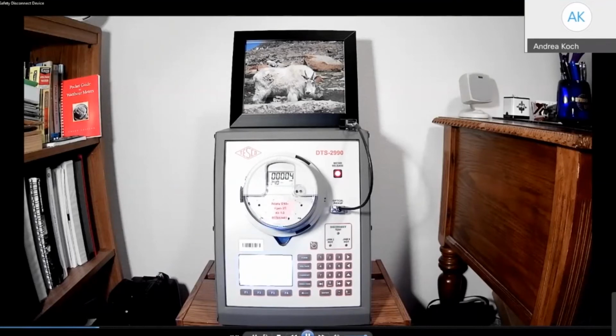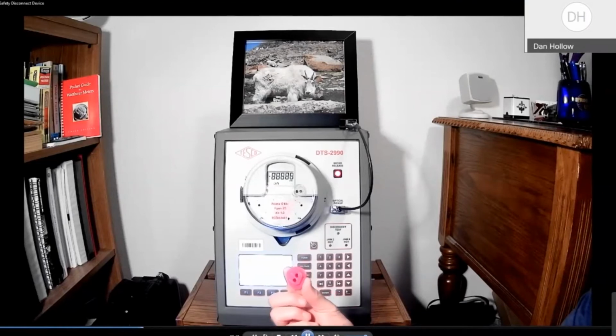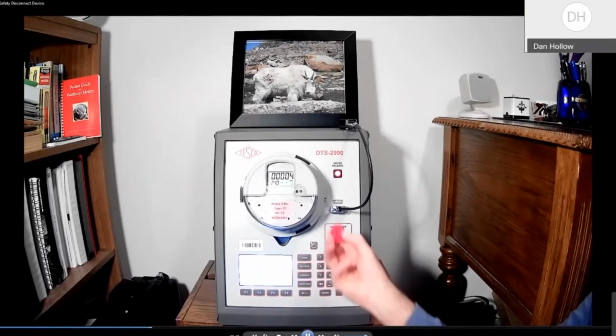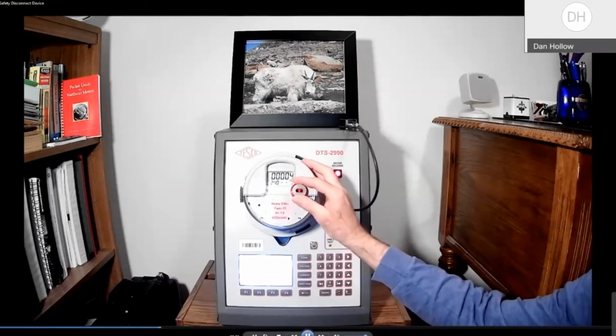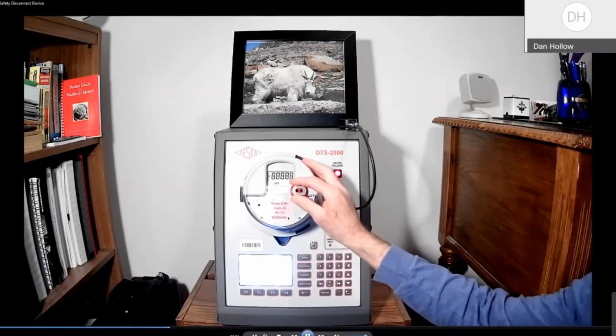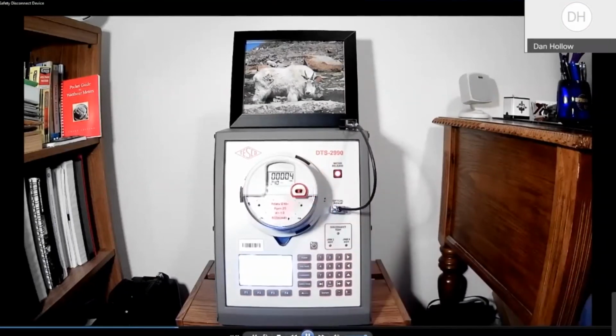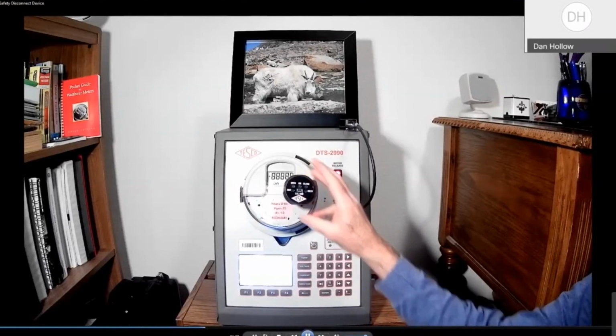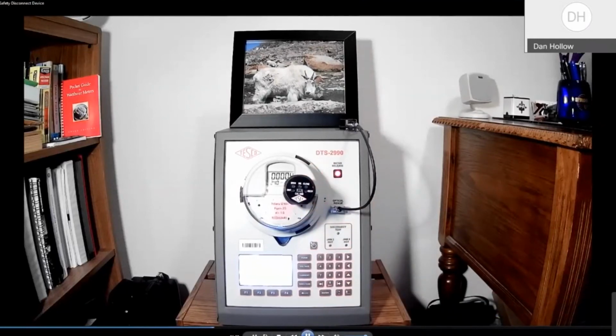This is a standard class 200 form 2S residential meter. This is an Aclara i210 Plus meter. This particular meter does not have the metal plate on the optical port, so we're going to use this little gadget here that will go on the front because it's just got a raised plastic ring. Now that snaps in there plenty tight. Then we'll take the safety disconnect device and put it on the front. It has basically 3 buttons, and that's all there is to it.